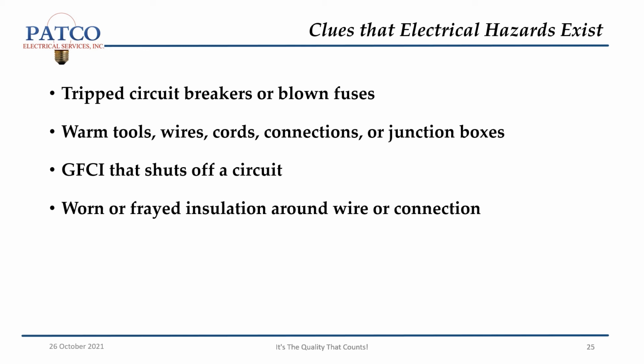Clues that electrical hazards exist: tripped circuit breakers or blown fuses, warm tools, wires, cords, connections, or junction boxes, a GFCI that shuts off a circuit, worn or frayed insulation around a wire connection. If you see any of these, feel any of these, make sure you figure out what's going on before you continue work. You need to fix that hazard.